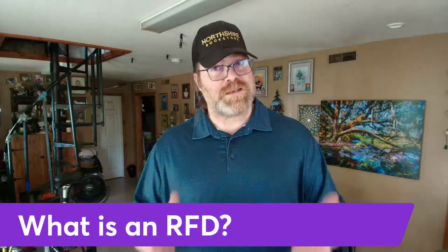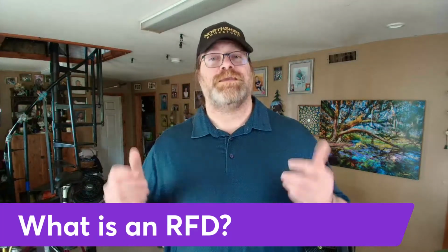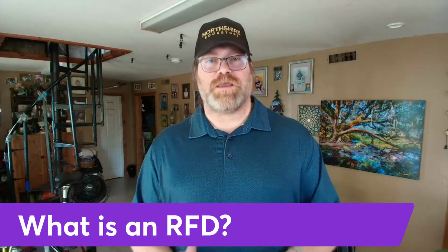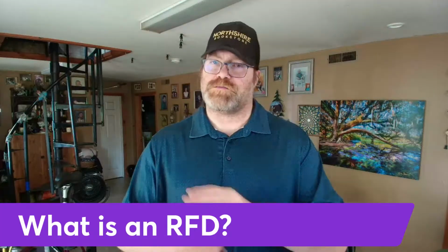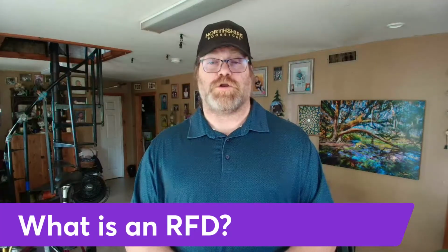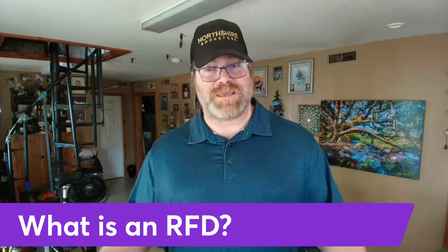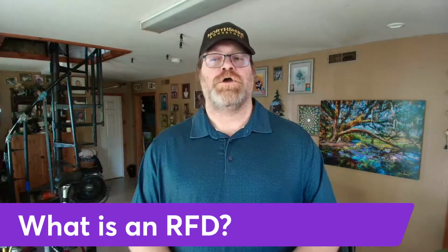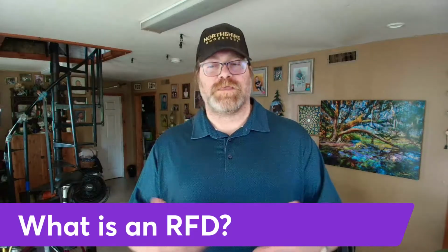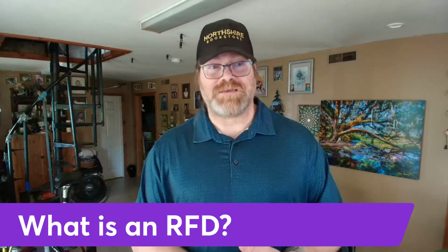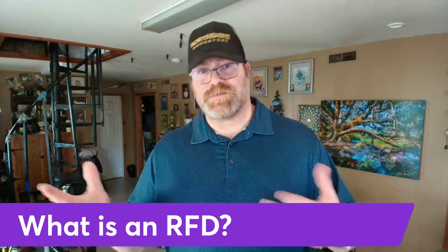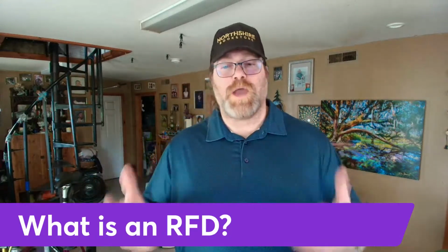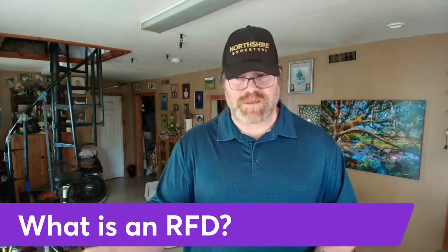But if you're doing something novel, the answer might be, yes, we've done a pre-RFD and we got a good determination from the Office of Combination Products. No, this is not a combination product. Or they could have said, yes, it is, and you had to follow up with an RFD and formally get the designation that CDRH has jurisdiction over this. So sometimes these happen, sometimes these don't happen. You have to go through the process.